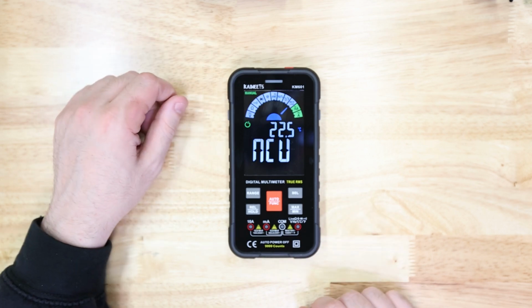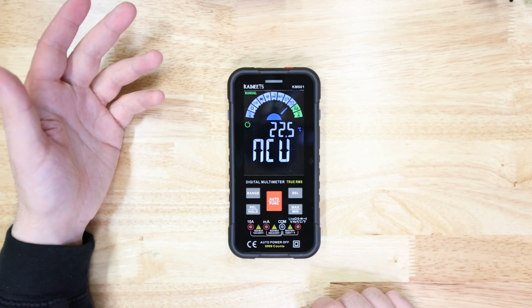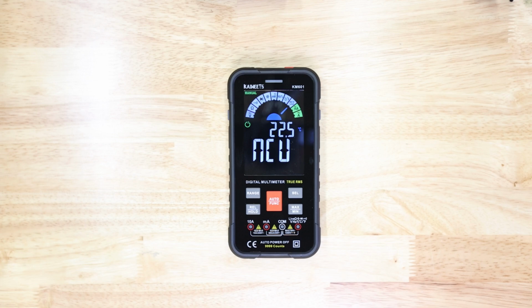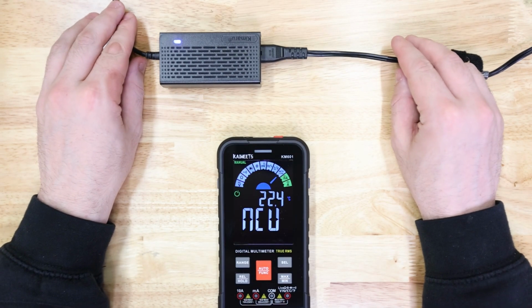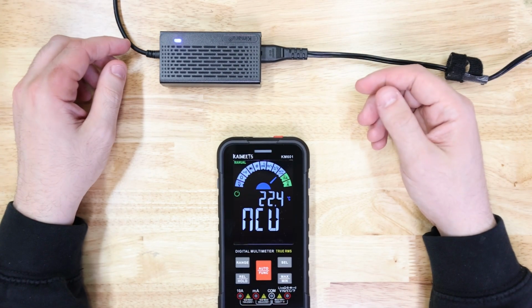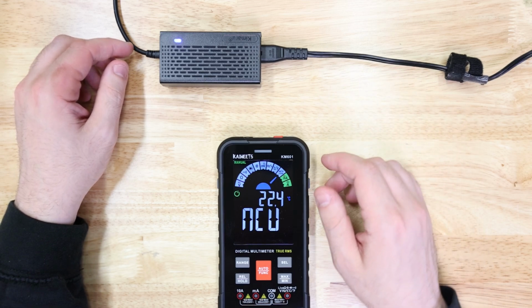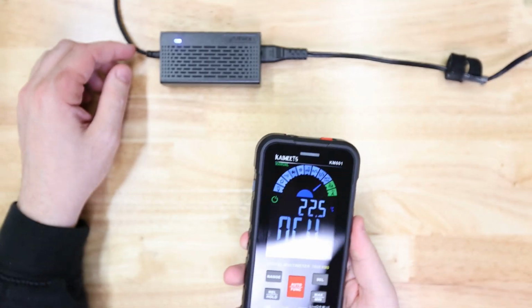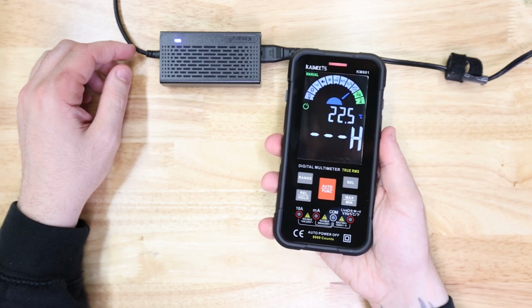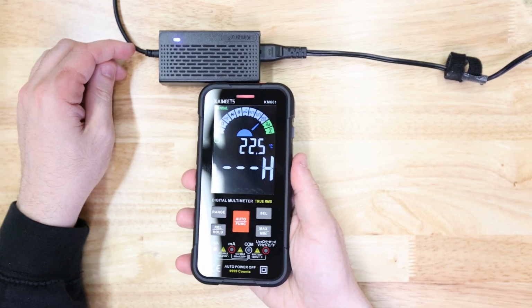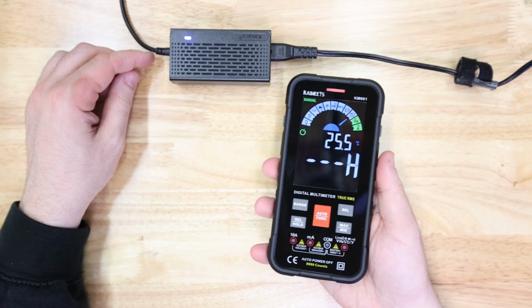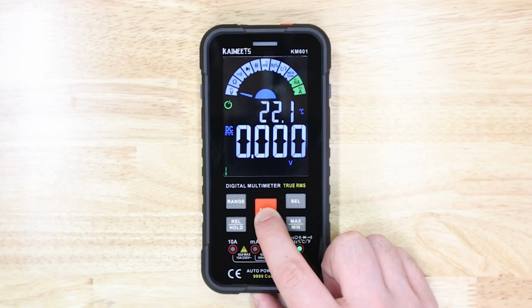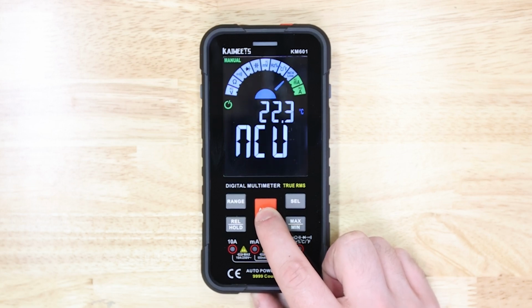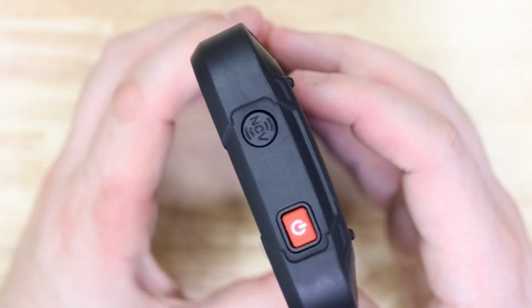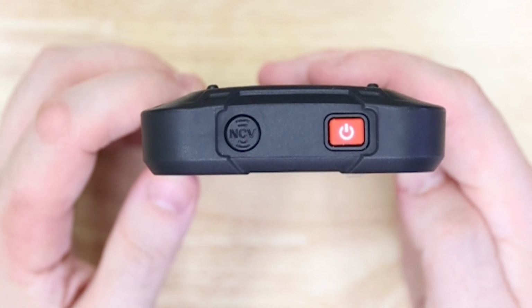The final mode we'll check out today is called the non-contact voltage detector, or NCV. The non-contact voltage detector does exactly what it says. It detects voltage running through our system without actually having to make physical contact with any of the wires. This is a simple and safe way to determine if the wires we are working with pose a hazard to us. First thing we'll do is switch to the NCV mode on our multimeter. This mode does not utilize the probes, only the sensor at the top, which we identified earlier in the video.